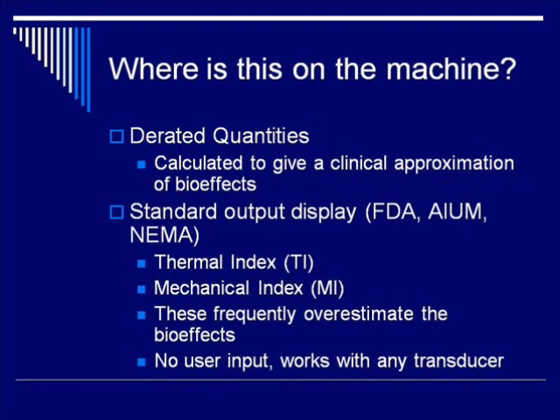If you've played with an ultrasound machine for any length of time, you'll notice that you haven't seen any of the alphabet soup we just discussed on your machine. That's because instead of calculating these numbers, we use a variety of derated quantities that give you a clinical approximation of the bio-effects that you may see clinically. We have a standard output display format for these numbers that has been agreed upon by the FDA, AIUM, and NEMA.